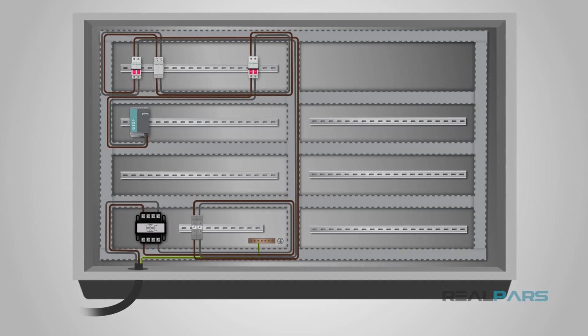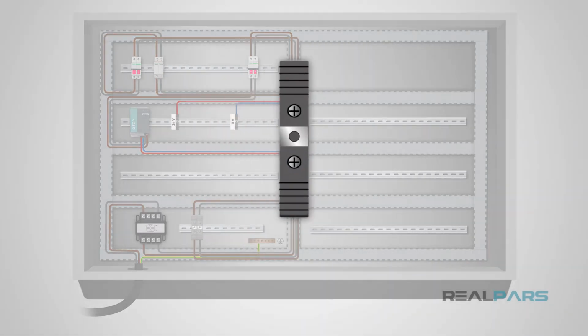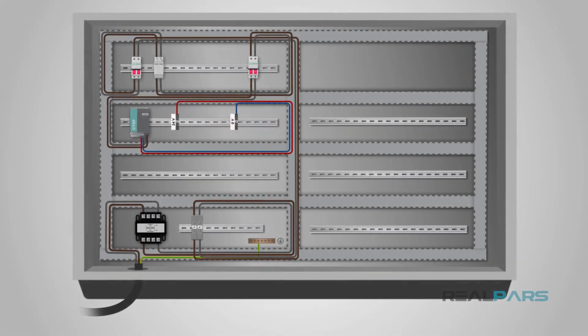Now that the control panel has incoming power from the main circuit breaker and power distributed by a transformer or power supply, the different voltages can be wired into terminal blocks for even more routing of power throughout the control panel. A terminal block consists of two terminals that can join two or more wires together. Terminal blocks can be arranged with several other blocks in a strip mounted on a DIN rail to run power from one source to several devices throughout the panel.